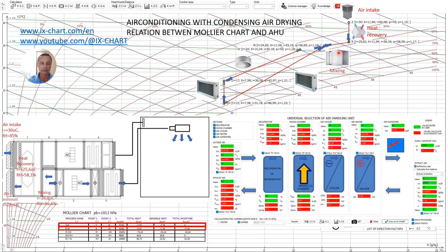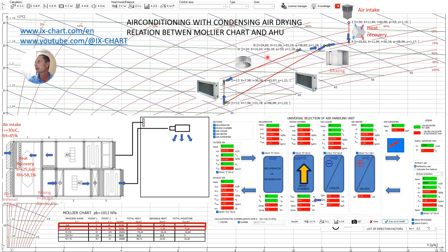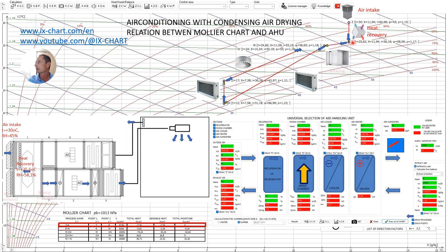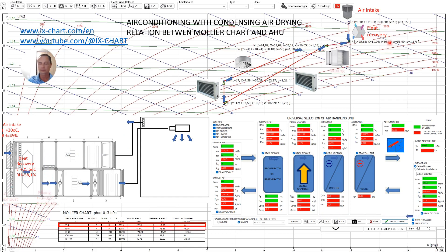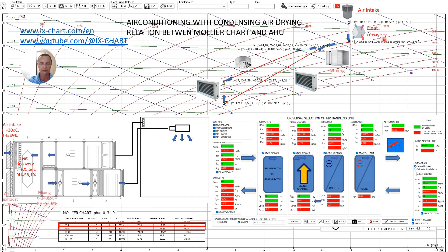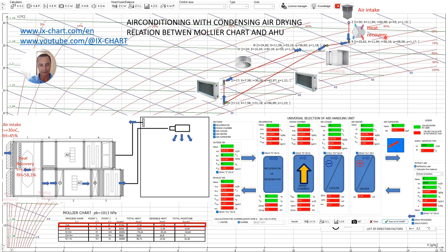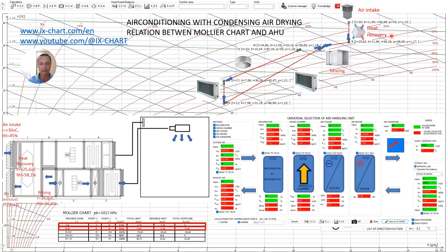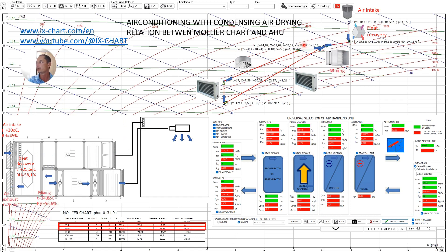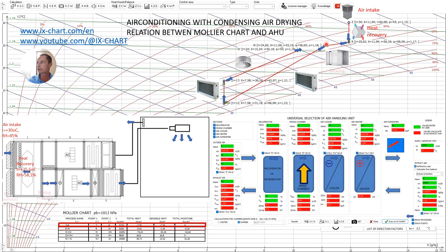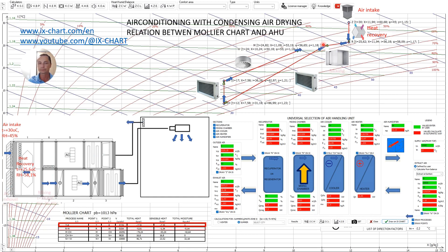Here after mixing we have enthalpy of 50 to 53 kJ per kilogram and the fresh air is 56 kJ per kilogram so making mixing economically possible and reasonable. So in the mixing chamber we combine half of the fresh air with the half of the air from the room and the result is point M.